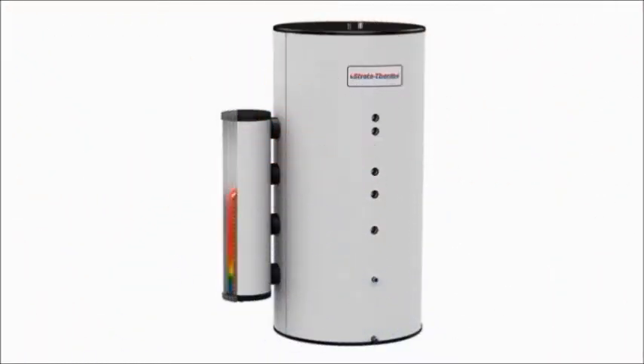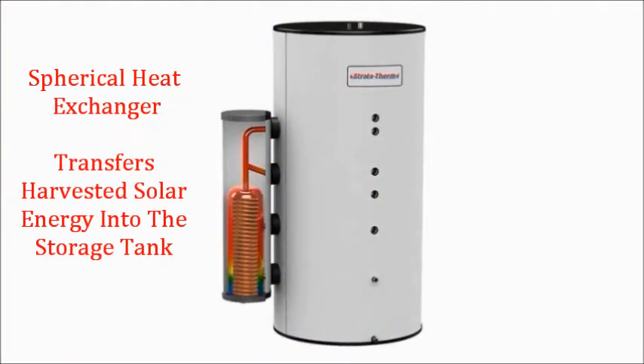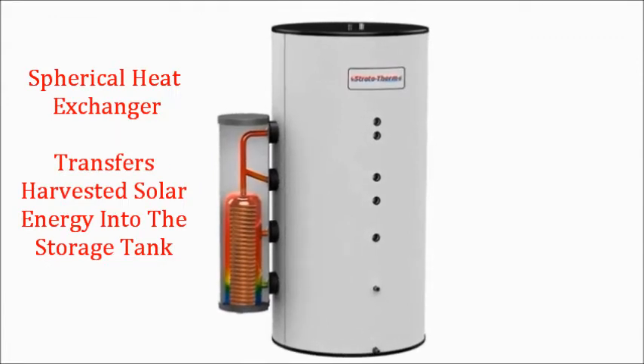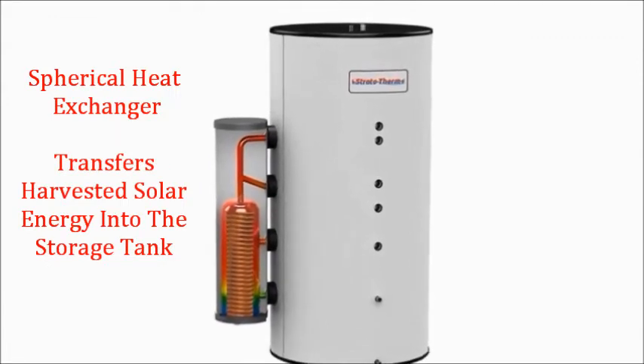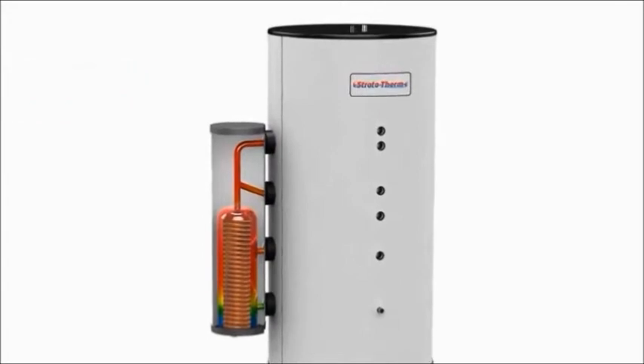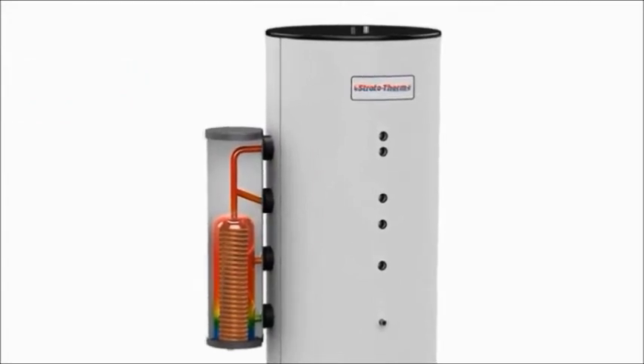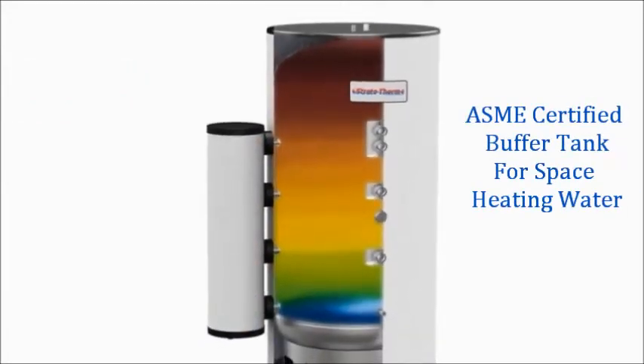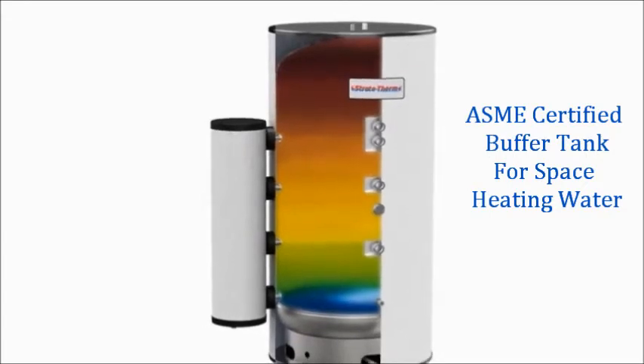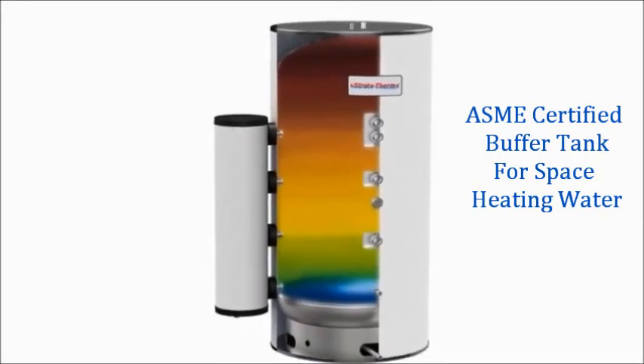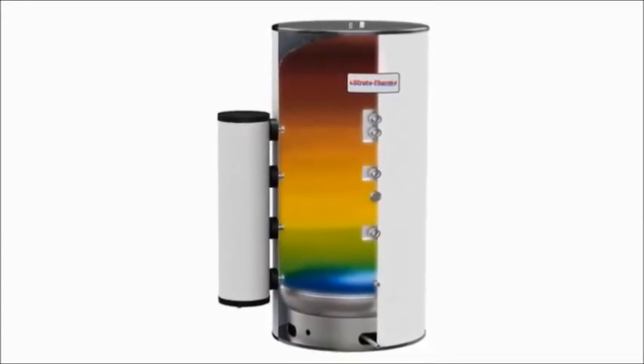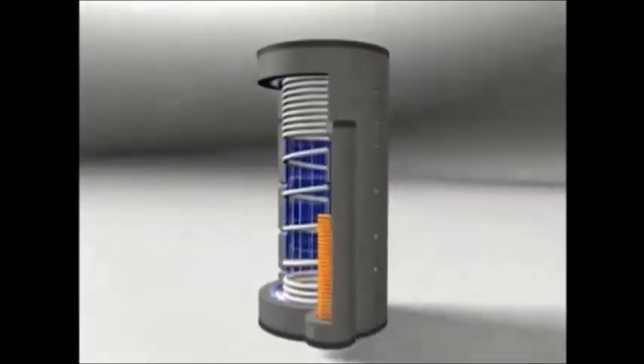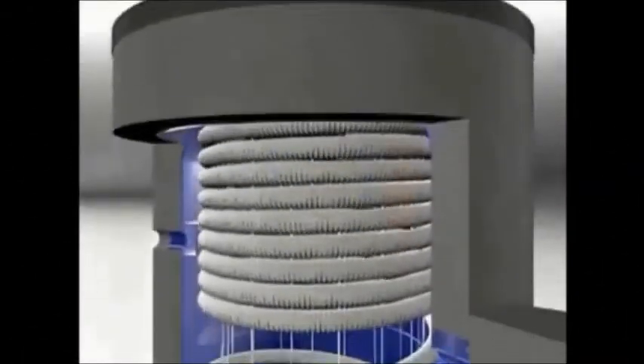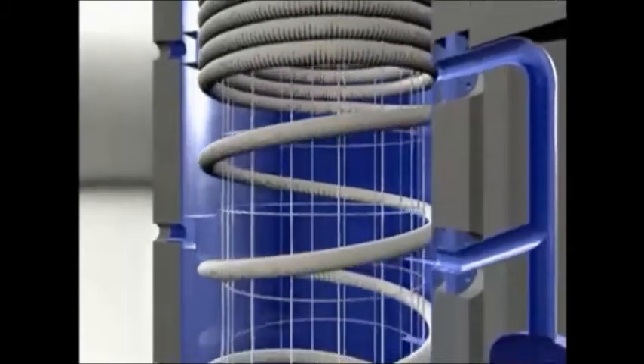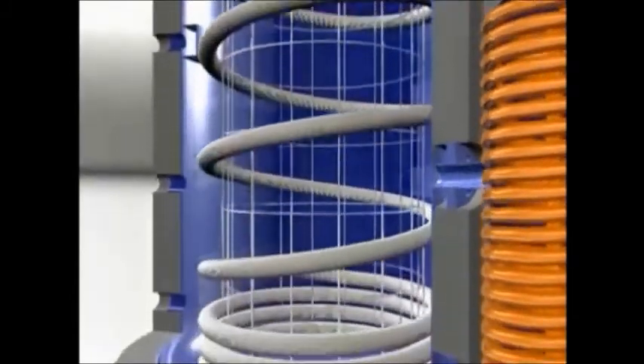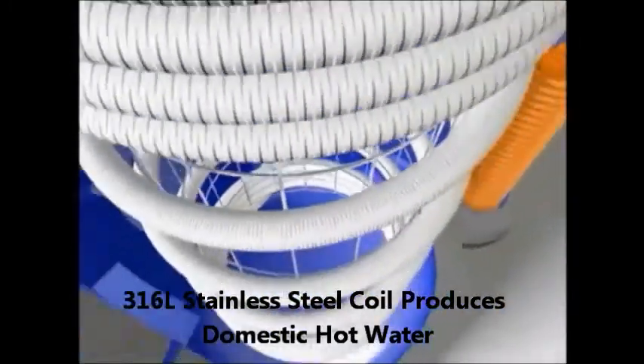On the left side of the storage tank is an externally mounted spherical heat exchanger, which includes an internal copper coil used for transferring solar thermal energy from the collectors to the tank. The storage tank is an ASME unlined vessel which contains hydronic heating water and acts as a buffer tank or hydraulic separator for the space heating system. Finally, on the inside of the storage tank is a large diameter corrugated 316L stainless steel coil. It's used to produce domestic hot water. Think of it as a reverse indirect water heater.